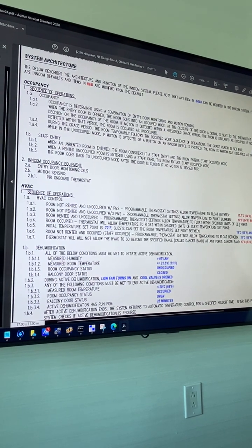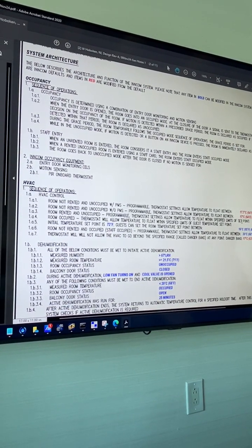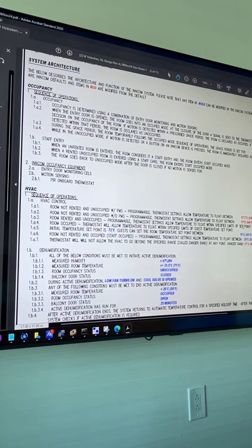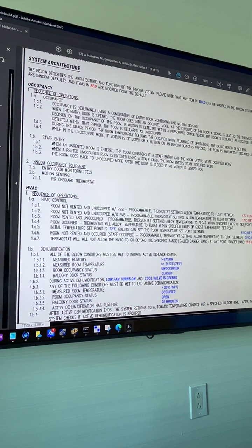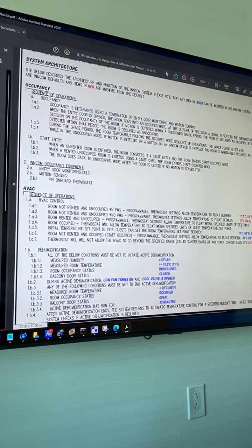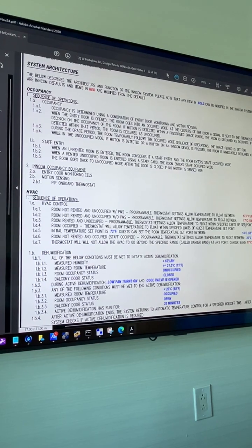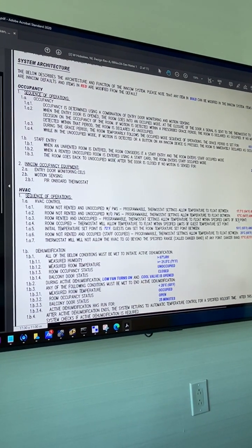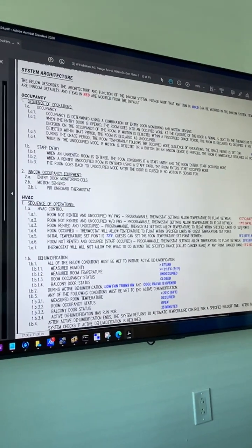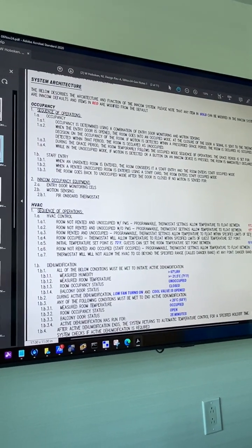That's just the general functionality, to try to go unoccupied as quick as possible based off of all the sensors in the room. So the more sensors you have, the quicker of a duration you can go unoccupied. But yes, any of these parameters are adjustable. Great. So, guest selectable band is 65 to 80. VIP mode, as I showed, is 62 to 85. So if according to the property management system the room's not rented, and there's staff in the room, it will try to keep the temperature between 68 and 75. Perfect. Okay. Can you bring up that trunk just to show the edge routers? Yes. Might be a good thing for us.